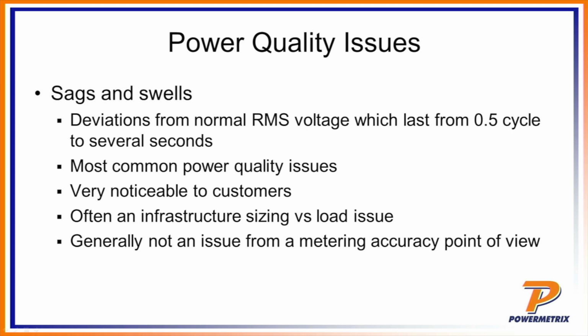Sags and swells are some of the most common power quality issues we see today. It's very noticeable to customers because the voltage, of course, has a direct effect on your equipment. Lights, of course, good old-fashioned incandescent lights, really require that the light output is going to be proportional to the voltage. So if you still are using incandescent lights and you see a large sag or swell, that will result in the lights notably either dimming or getting brighter.